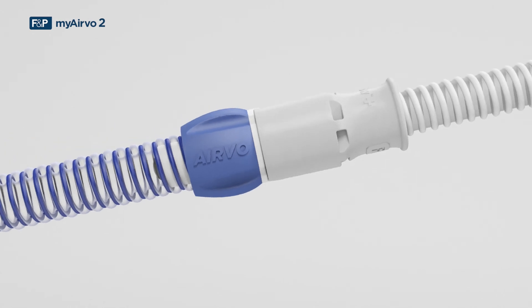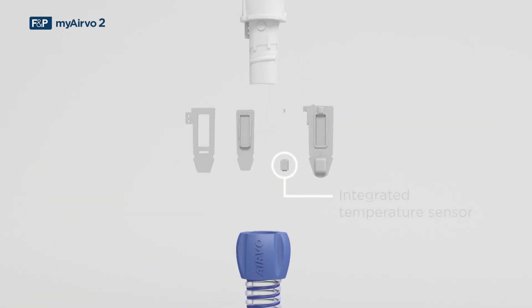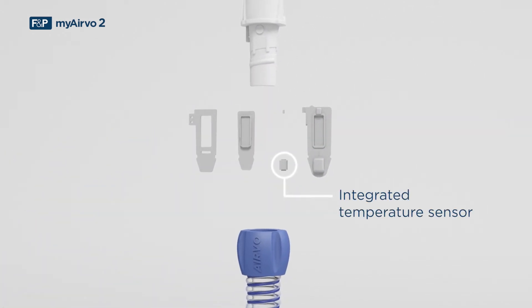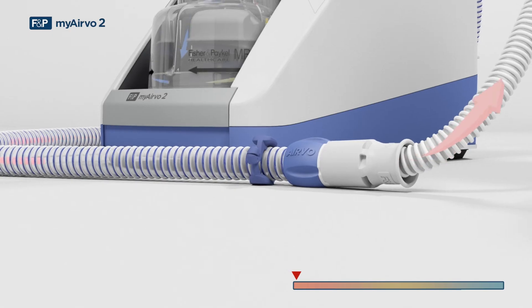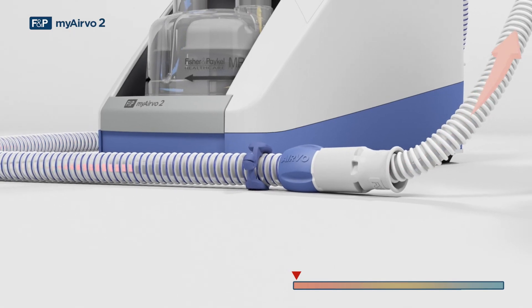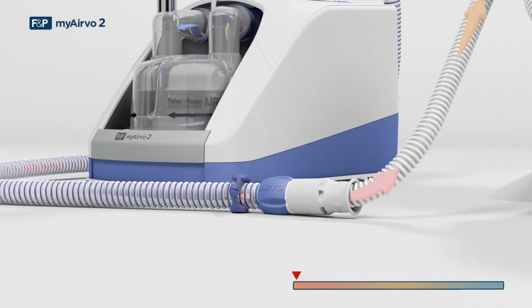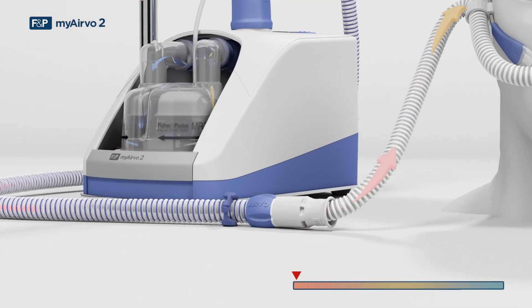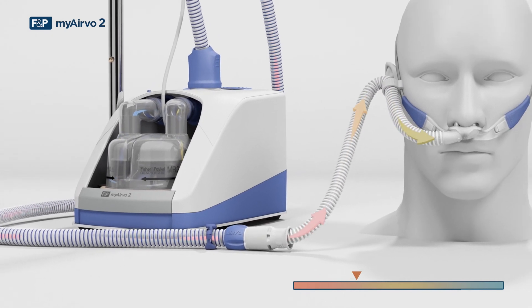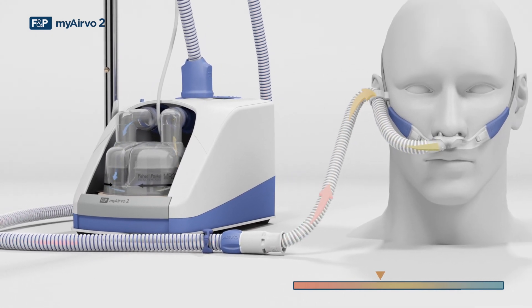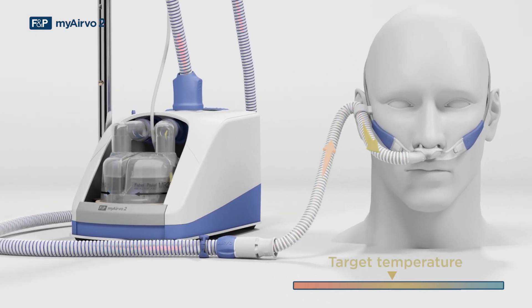At all parts of the system the gas temperature is measured and fed back to the myAirvo algorithm. This gives a precise understanding of the changing temperature across the system and enables it to compensate for the temperature drop across the cannula, ensuring it reaches the patient at the target temperature.